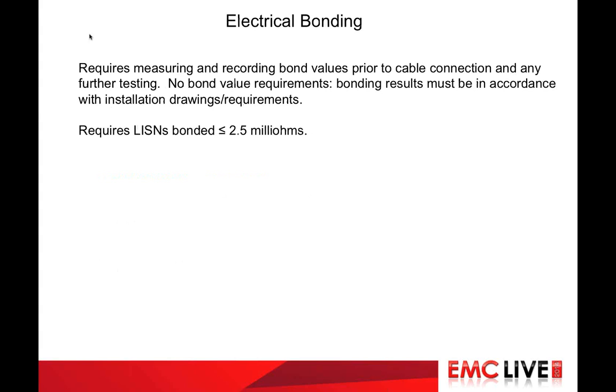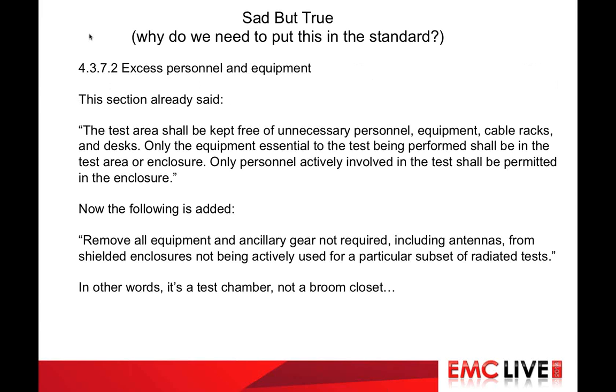All right, the first change we cover here is an expansion on the previously existing electrical bonding section. It now requires the measurement and recording of bond values prior to cable connection and any further testing. There are no test sample bond value requirements because bonding results must be in accordance with equipment-specific installation drawings and requirements, as always. The standard requires LISNs to be bonded to the ground plane with a DC resistance of less than or equal to 2.5 milliohms. This addendum is just a standardization of what we hope everyone is already doing. So file this change under sad but true.